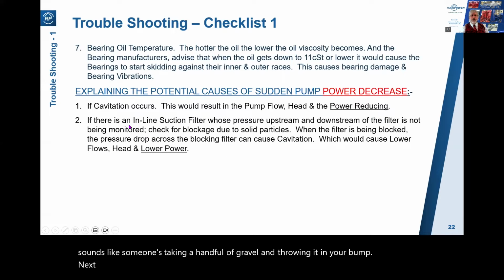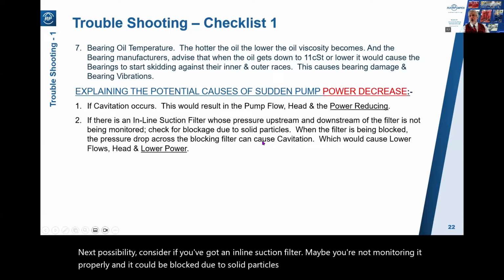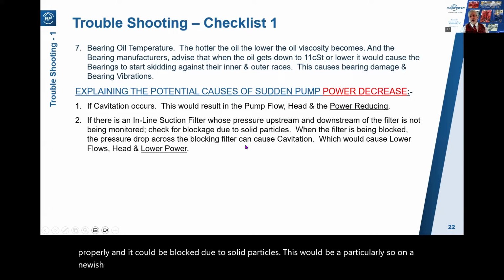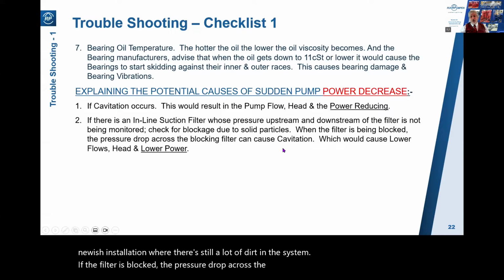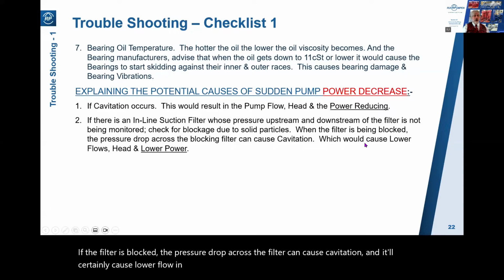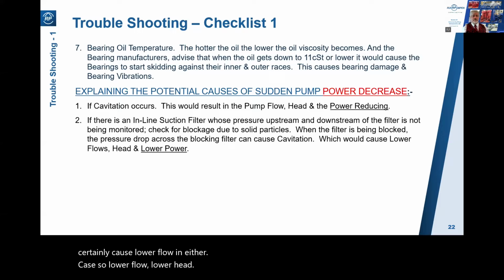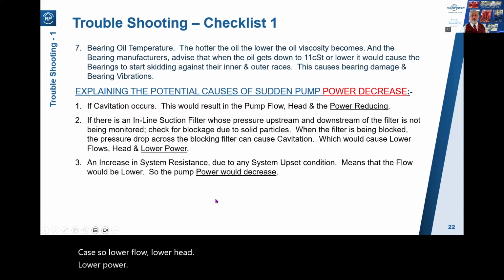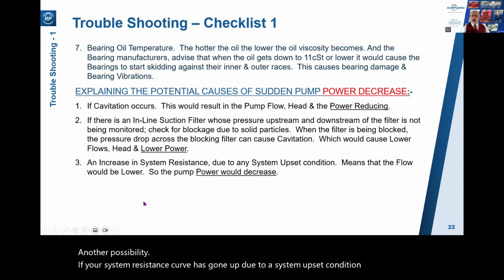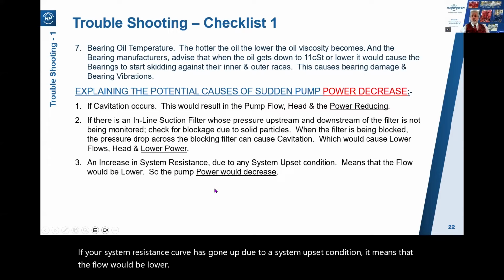Next possibility, consider if you've got an inline suction filter. Maybe you're not monitoring it properly and it could be blocked due to solid particles. This would be particularly so on a newish installation where there's still a lot of dirt in the system. If the filter's blocked, the pressure drop across the filter can cause cavitation, and it'll certainly cause lower flow in either case. So lower flow, lower head, lower power. Another possibility, if your system resistance curve has gone up due to a system upset condition, it means that the flow would be lower. So the pump power would decrease.